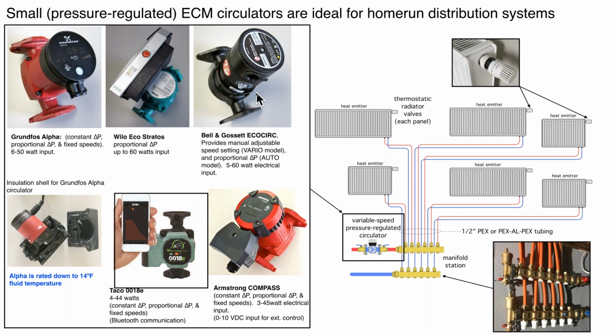Some of these circulators can tell you the flow rate going through them at any time. They can also tell you the wattage that the circulator is operating at. Taco just introduced this one, the 0018. That actually has Bluetooth connectivity. It can go right to your phone, and you can bring it up and see exactly what it's doing in terms of flow rate, wattage, and so forth. And it's the ideal, any of these circulators are ideal to tie in with that home run distribution system. This is just showing you a manifold station with 1/2-inch tubes going out to the different radiators, some air vents over here. Again, very, very repeatable, okay?